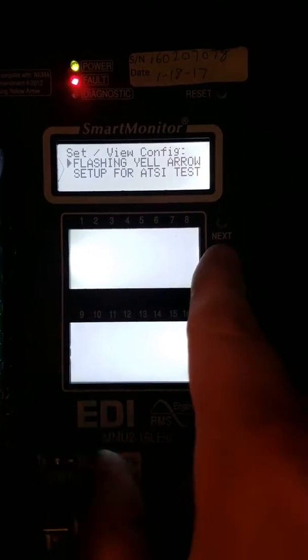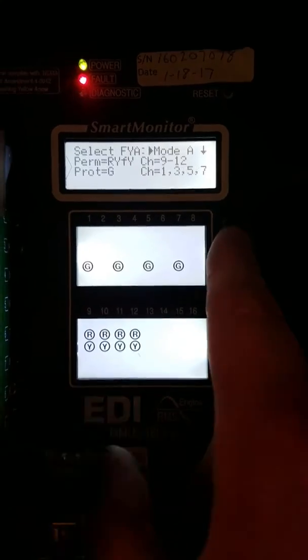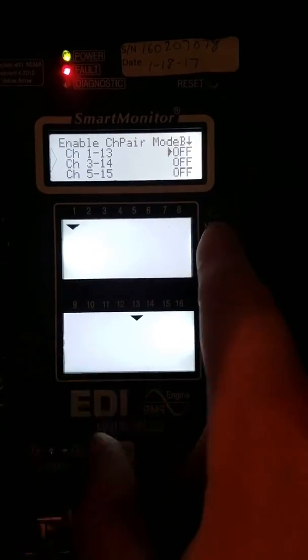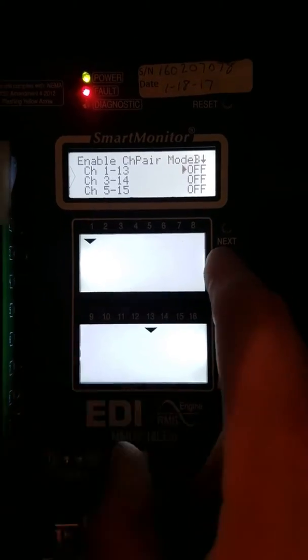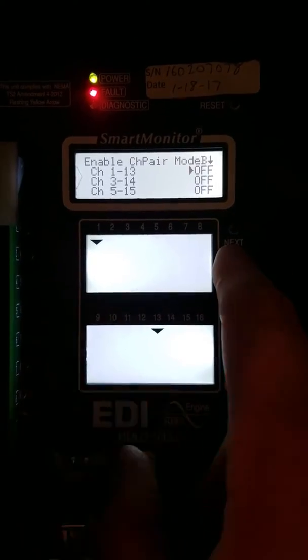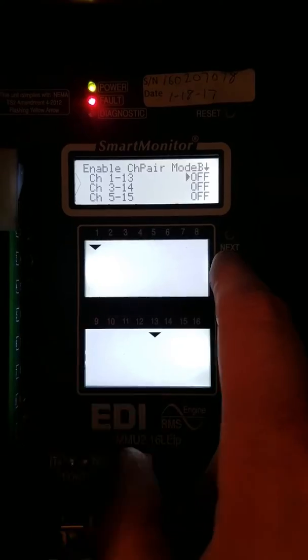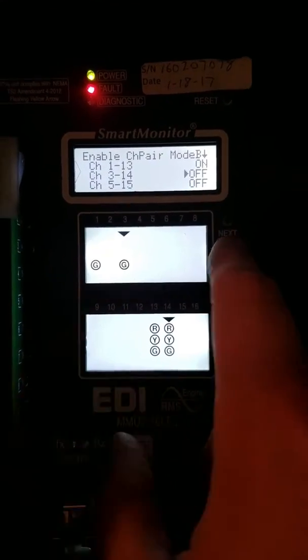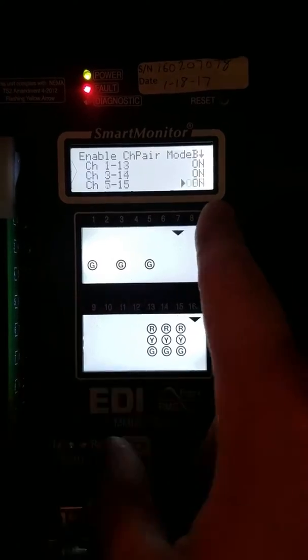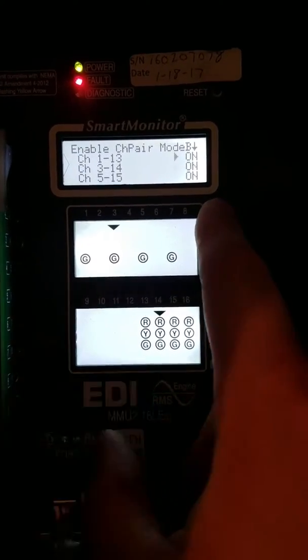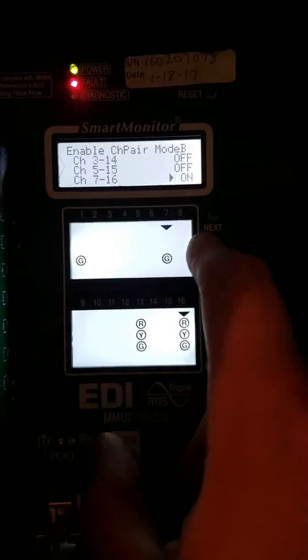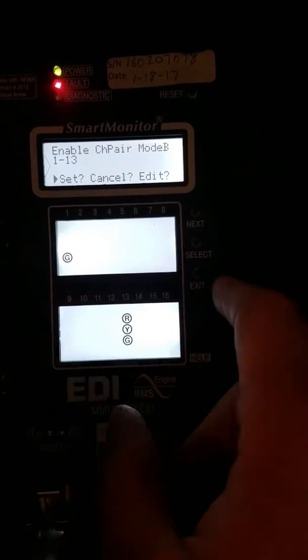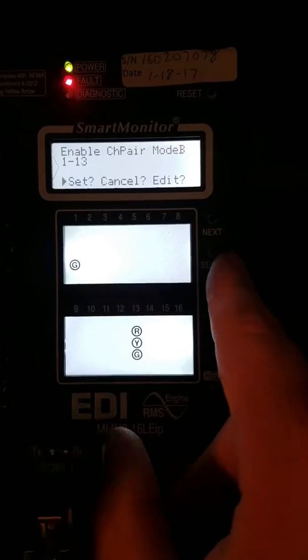Now we're on flashing yellow arrow already, so we're just going to hit Select again. We're going to go to Mode B, Select. We're running just Channel 1, Phase 13. If we were running any of the other left turns, then you would turn these on. So we're just going to hit On there. Since we're not using those, we'll just turn those off. Hit Exit, and then Select.